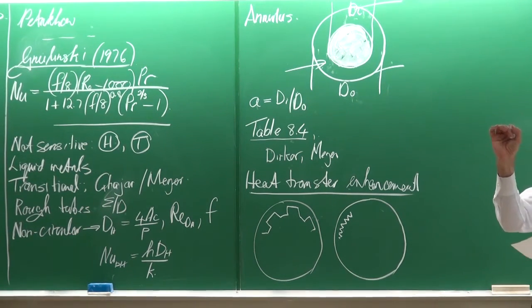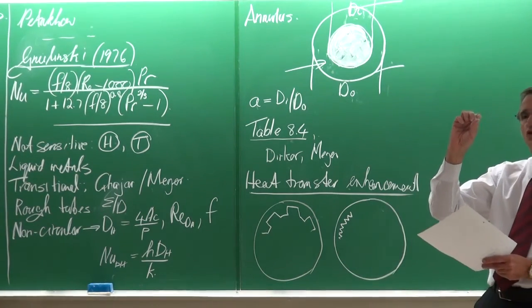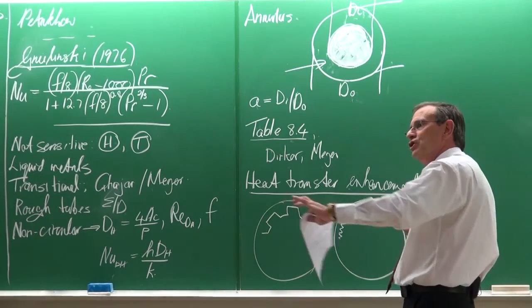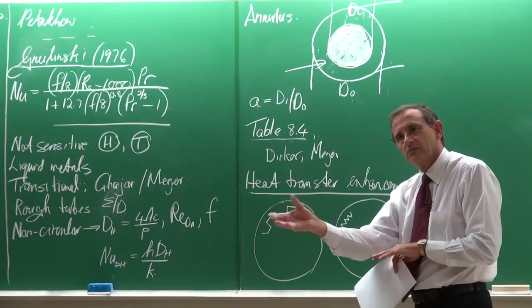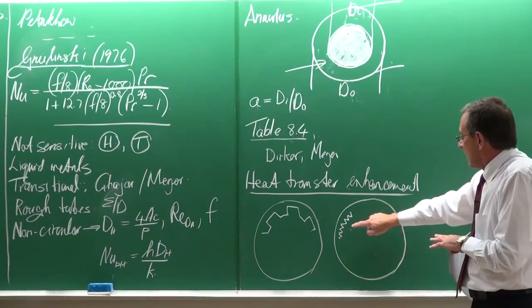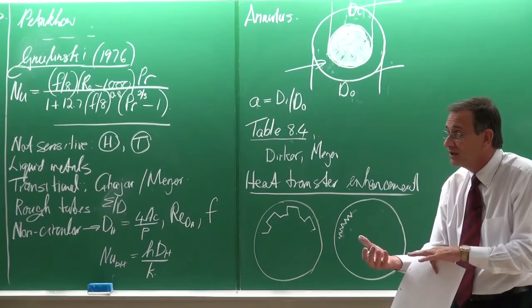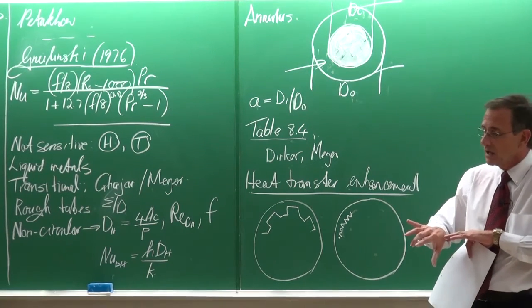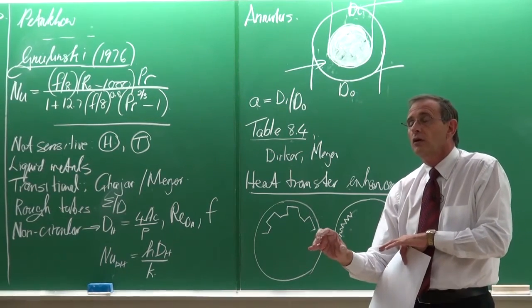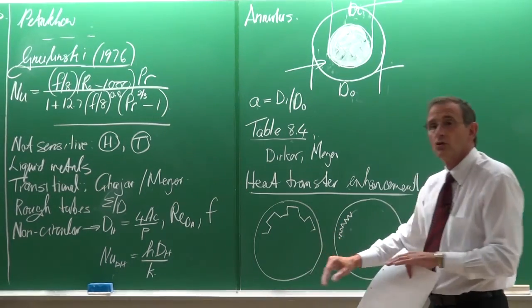Typically in a 8 to 12 diameter tube, there would be 80 fins on the inside and their height is just about 0.4 millimeters. But these fins do not just run in a longitudinal direction, they are being rotated like in a rifle.